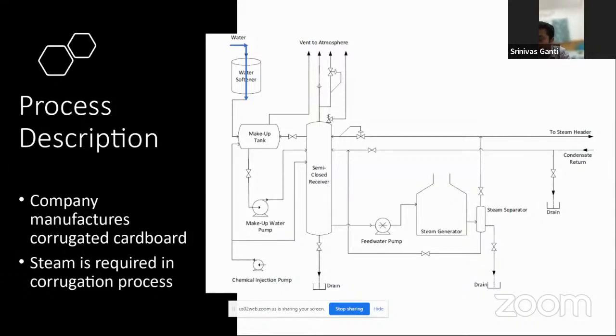So keeping that in mind, they get water from the city supply, and they have a water softener as well, which will go into a makeup water tank, which will act as a surge drum for them in case of any disruption from the city water supply. Then they will supply that makeup water. Along with it, there is some chemical injection as well to treat the water, and it will go to one vessel called the semi-closed receiver. I'll go into details of the semi-closed receiver after completing the flow.